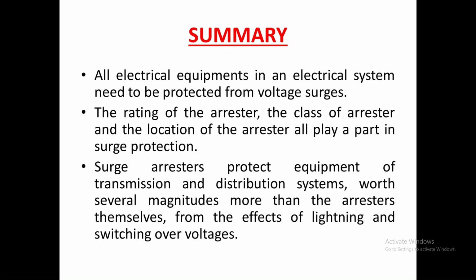So, as we know, all electrical equipments inside an electrical system or substation need to be protected from voltage surges, and the rating of the arrestor based on the substation rating, the class of arrestor, and the location of arrestor play a very important role for the protection of the devices. And it is very much essential equipment inside a transmission or a distribution substation.